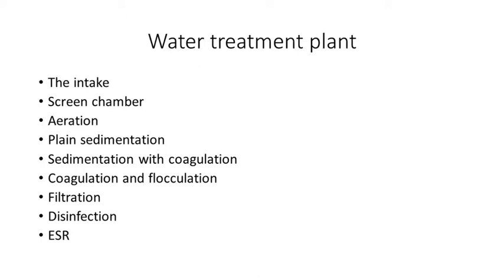After that, the next one is aeration. The basic purpose of aeration is to increase the oxygen content of the water and remove bad odor gases like CO2 and H2S. The principle of aeration is gas transfer, where the water comes in contact with atmospheric air, so that atmospheric oxygen is dissolved into the water, and the bad odor gases present in the water are released into the atmosphere. That is aeration.